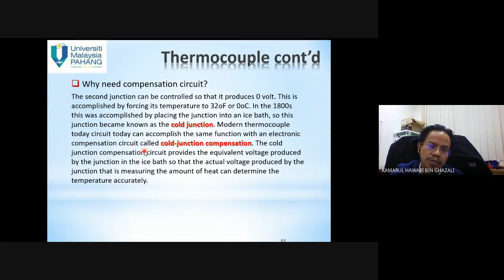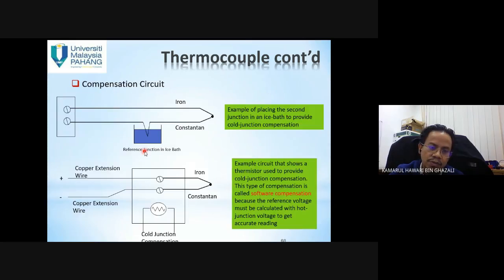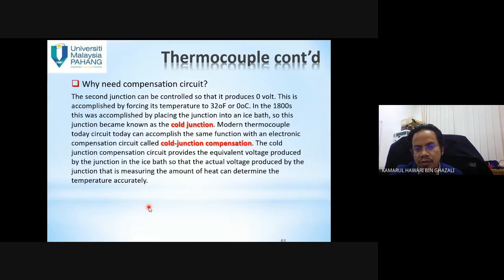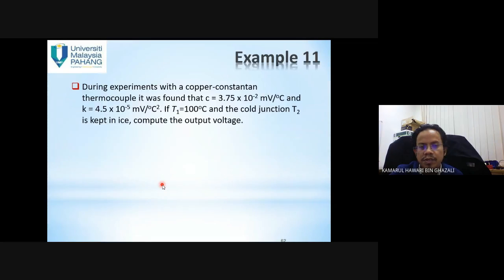Modern thermocouple circuits today can accomplish the same thing with an electronic compensation circuit called cold junction compensation. So we just use this cold junction compensation. This is the old way to do the compensation. This is the new one. We just use this. We have a circuit, they call it a compensation circuit. It provides the equivalent voltage produced by the junction in the ice bath, so that the actual voltage produced by the junction that is measuring the amount of heat can determine the temperature accurately.